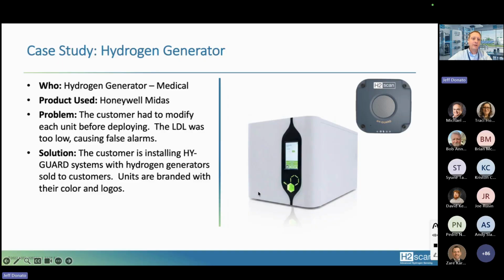This is one that we've been working on. It's a medical application, hydrogen generator. They were using a Honeywell Midas, and the problem they were having is that they had to modify each one of the hydrogen sensors before they used it, before deploying it to their customer. The lower detection limit was way too low, which is a good point for a lot of applications.